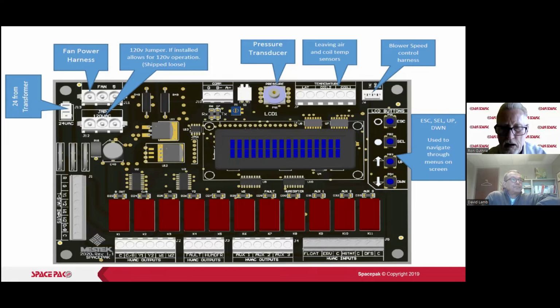Auxiliary contacts. You can program if you want to bring something on. I use them as a workaround for having an old zoning panel and thermostats that wouldn't bring on my electric heat at the same time as my heat pump. So those are there. Use them how you need to use them or not use them. You guys can get pretty creative in the field. You're used to doing that every day. So they are there, and just know that you can program which contacts to come on. There's a default, but you can program which auxiliary contacts will come on depending upon the mode that you're in.